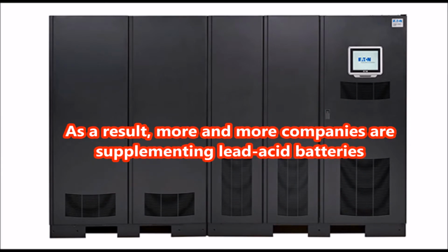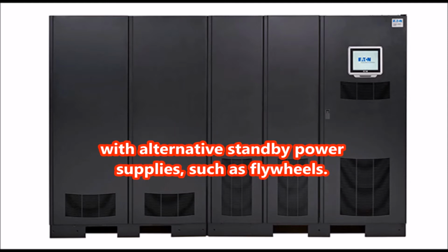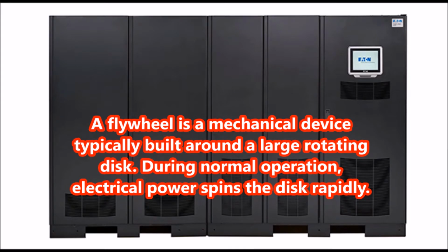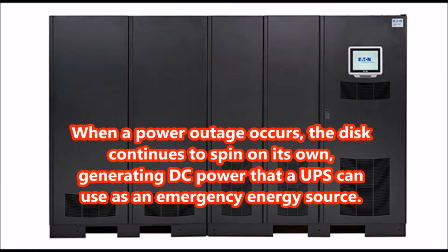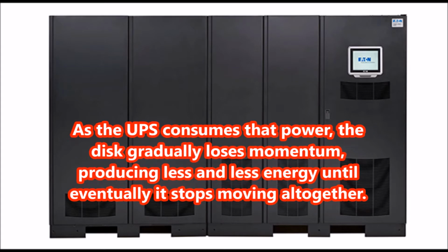As a result, more and more companies are supplementing lead-acid batteries with alternative standby power supplies, such as flywheels. A flywheel is a mechanical device typically built around a large rotating disc. During normal operation, electrical power spins the disc rapidly. When a power outage occurs, the disc continues to spin on its own, generating DC power that a UPS can use as an emergency energy source.